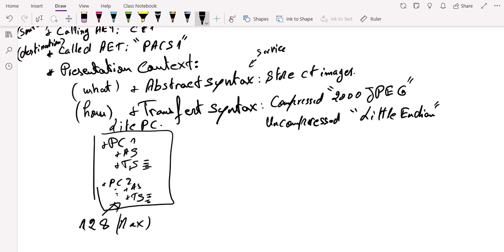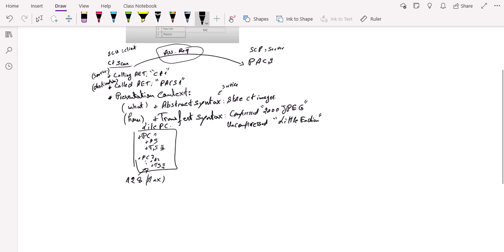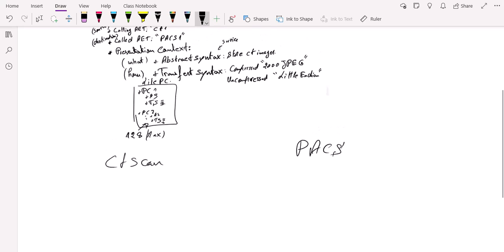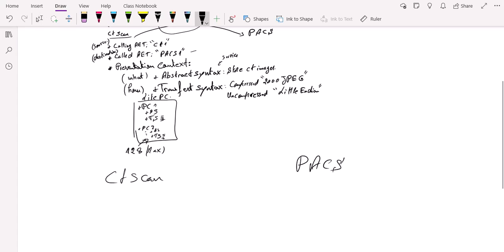And then the PACS will choose, and will compare this information to its presets, and it's going to send back a list, including the supported services. So PACS will review the AE titles and verify that the AE title matches his one, this PACS one. So we're going to understand that this request concerns him, and he's going to also examine the source AE title to ensure that communication is permissible, and checking for any restrictions on that device.